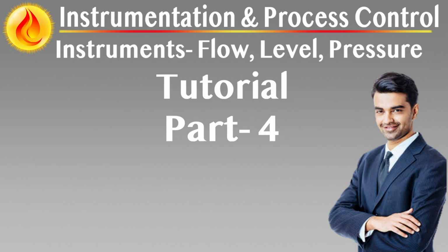Mass flow direct from sensor, no pressure or temperature compensation required. Thermal dispersion meters calculate mass flow directly without relying on inferred calculations or downstream compensation. This makes them particularly useful where density varies significantly, e.g. outdoor air, off-gas. Space or cost prohibits separate pressure and temperature instruments. Simple, low-maintenance measurement is required without sacrificing reliability.